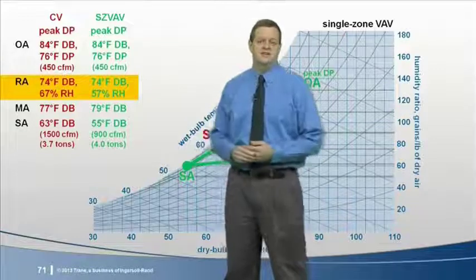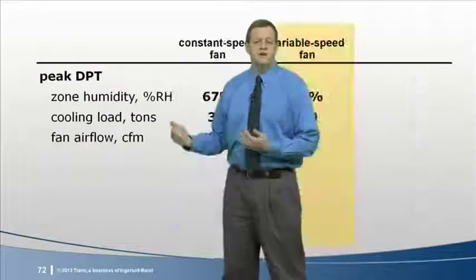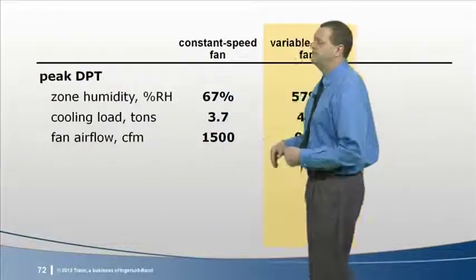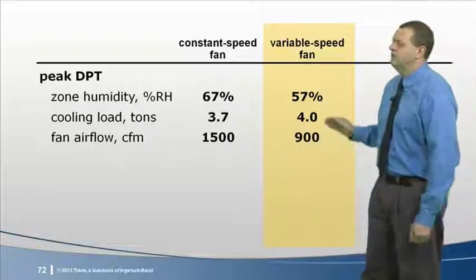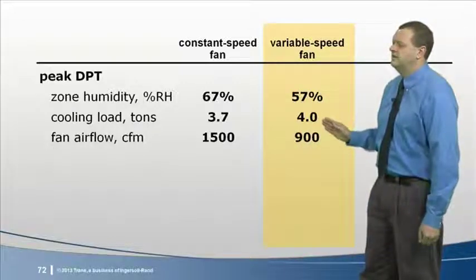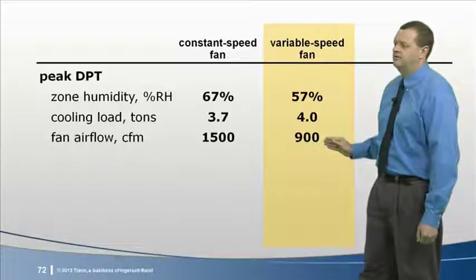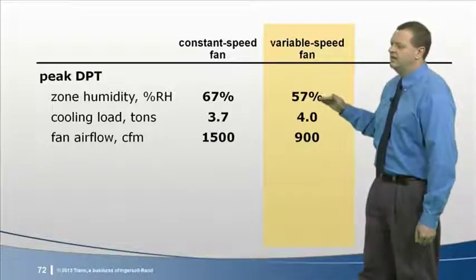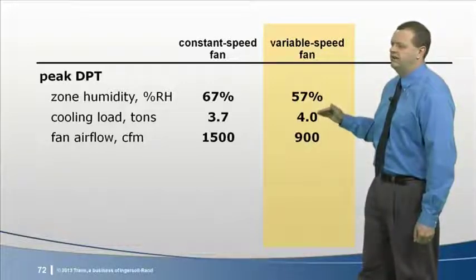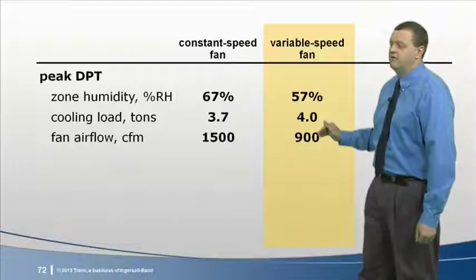A pretty significant improvement. Now in this comparison, for the variable speed fan system, the load in the cooling coil is 4 tons and the fan moves 900 CFM. So achieving this lower humidity level requires a bit more compressor energy while benefiting from much lower fan energy.